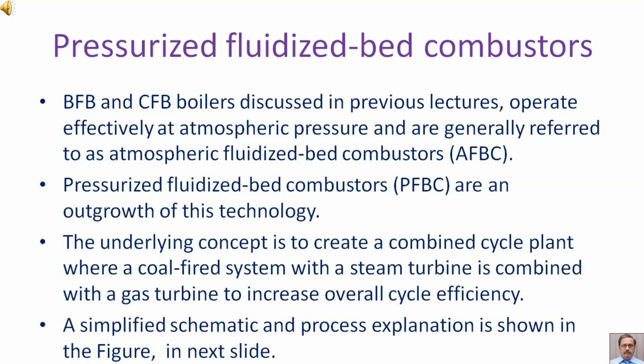BFB and CFB boilers discussed in previous lectures operate effectively at atmospheric pressure and are generally referred to as Atmospheric Fluidized Bed Combustion (AFBC). Pressurized Fluidized Bed Combustors (PFBC) are an outgrowth of this technology. The underlying concept is to create a combined cycle plant where a coal-fired system with a steam turbine is combined with a gas turbine to increase overall cycle efficiency.